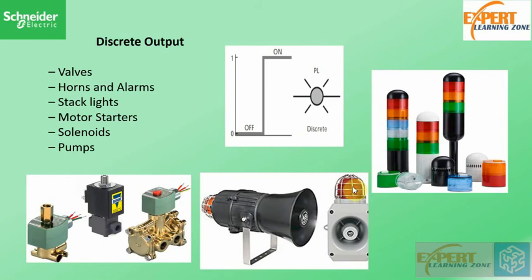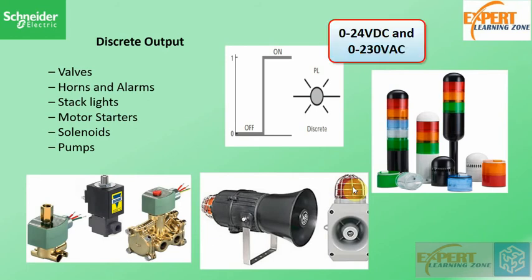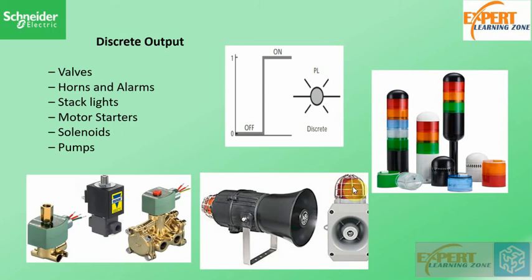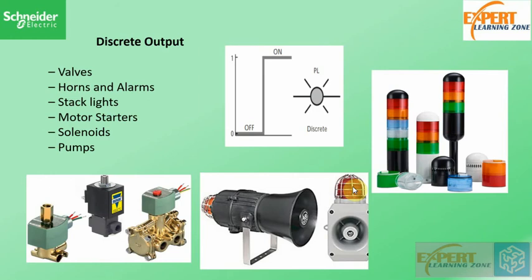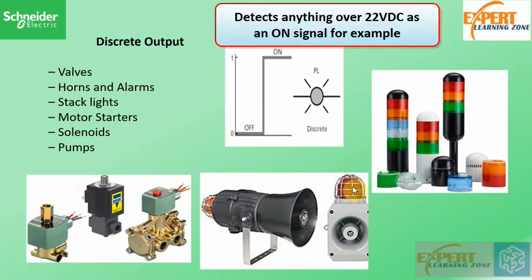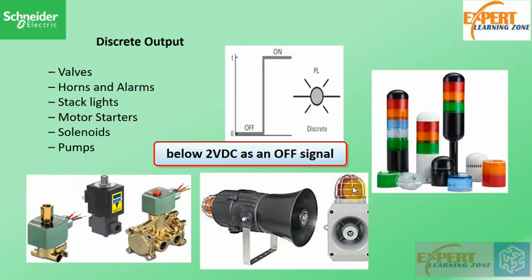The application of your control system will determine the type of discrete device you choose. There are a variety of discrete output devices and modules that can be used in a PLC system to send and receive on/off signals. These devices can be AC or DC and are available in different voltage ranges: 0 to 24 volt DC and 0 to 230 volt AC. Zero is the off signal and 24 volt DC or 230 volt AC is the on signal. Usually there is a threshold for the 0 to 24 volt DC which will detect anything above 22 volt DC as on signal and anything below 2 volt as off signal.